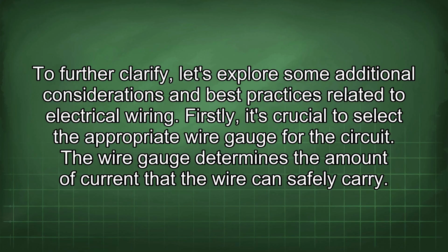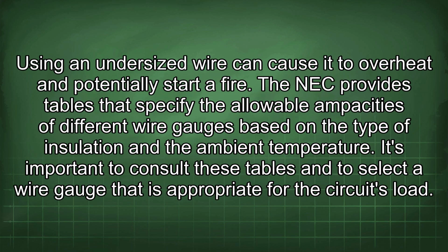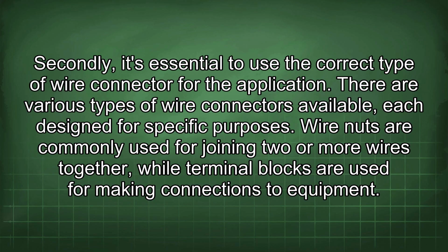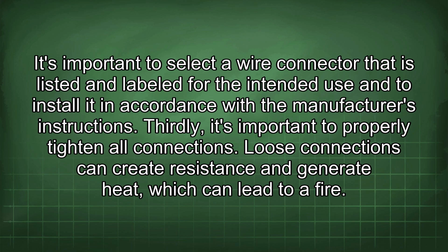Firstly, it's crucial to select the appropriate wire gauge for the circuit. The wire gauge determines the amount of current that the wire can safely carry. Using an undersized wire can cause it to overheat and potentially start a fire. The NEC provides tables that specify the allowable ampacities of different wire gauges based on the type of insulation and the ambient temperature. It's important to consult these tables and to select a wire gauge that is appropriate for the circuit's load. Secondly, it's essential to use the correct type of wire connector for the application. There are various types of wire connectors available, each designed for specific purposes. Wire nuts are commonly used for joining two or more wires together, while terminal blocks are used for making connections to equipment. It's important to select a wire connector that is listed and labeled for the intended use and to install it in accordance with the manufacturer's instructions.